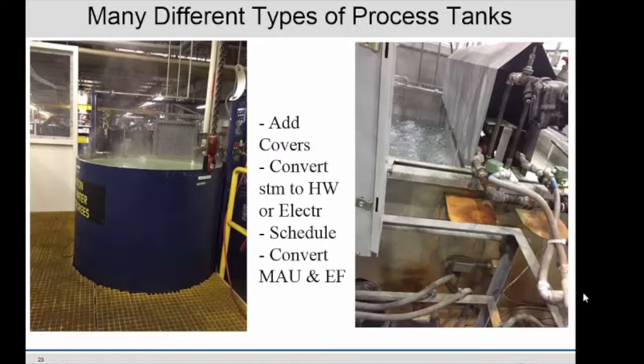This is a real job I'm doing right now, and these industrial buildings, they'll have these open tanks. They're uninsulated, boiling water. They're using steam to heat it, and they're just on all the time. So what we'll do is we'll go in and insulate the tank. We'll try to change from steam to hot water. You can't always get rid of all your steam. Where you do have steam, you do it very efficiently, okay? But we'll put these automatic closures on the tanks. So when they're not using the tank, close it. At night, when you're not there, turn it off. So we'll put in controls to do that, okay?